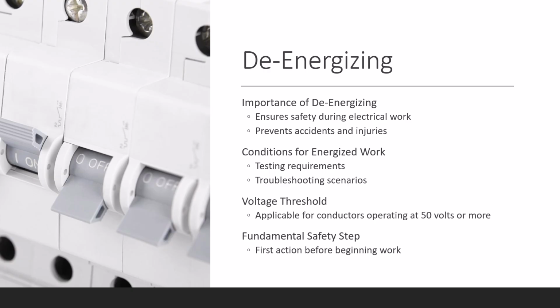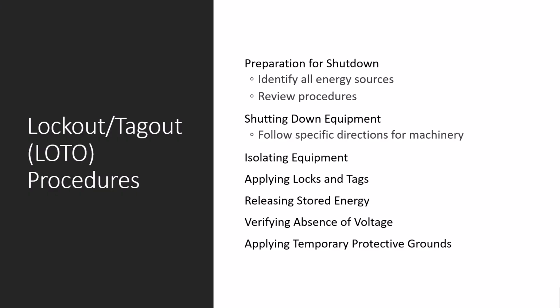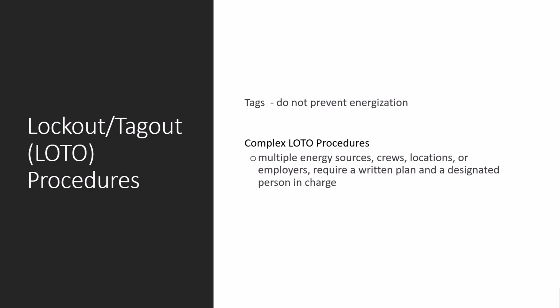The lockout/tagout procedure ensures equipment stays de-energized, involving steps like preparing, shutting down, isolating, applying locks and tags, releasing stored energy, and verifying no voltage exists. Locks physically stop accidental re-energization, while tags provide warnings. For complex situations, a specific written plan and one designated person in charge are essential.